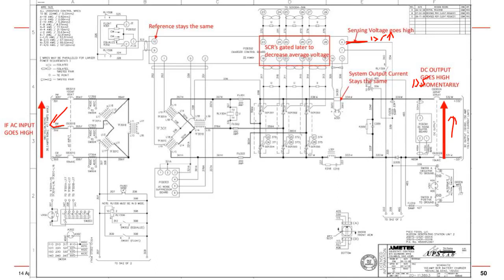The same is true if the AC input goes high. If the AC input goes high, the DC output momentarily goes high. The sensing voltage says we're not at 135 anymore, we've gone up for some reason, don't know why. So it tells the SCR to gate later in the cycle of the sine wave, which will decrease the average voltage until we get back to 135 volts.